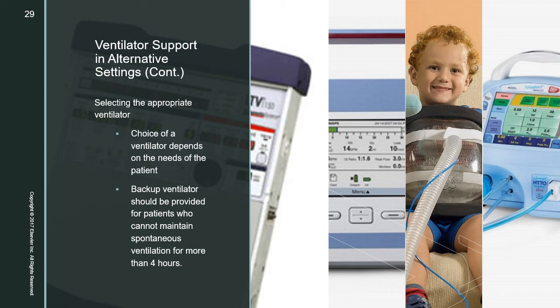Selecting the right ventilator. The choice of a ventilator for a patient in an alternative care setting should be based on the patient's clinical need and the available support services. In some cases, a patient may dictate that more than one ventilator be provided. A second backup ventilator should be provided for patients who cannot maintain spontaneous ventilation for more than 4 consecutive hours.